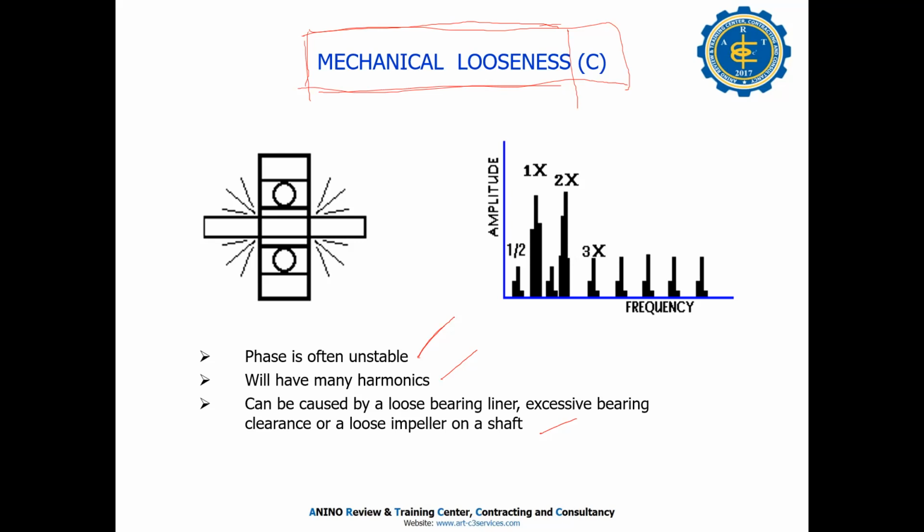That is deeper analysis. But as we are beginners in testing, commissioning, startup, and normal operation, I know this is the vibration of this pump. I know the history of this pump. Sometimes they call me, Francis, there is high vibration in the pump. What pump? The seawater pump A. How much vibration? Okay, that's normal. Because I have experience. But if you say the sidebands, I can do that.